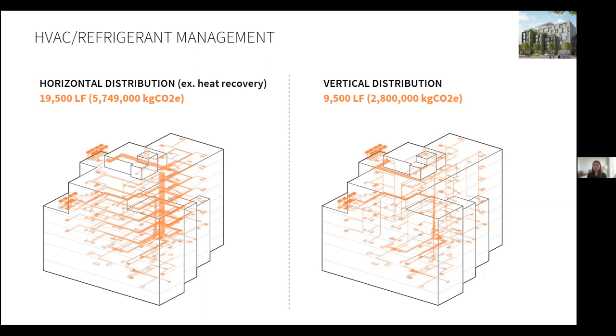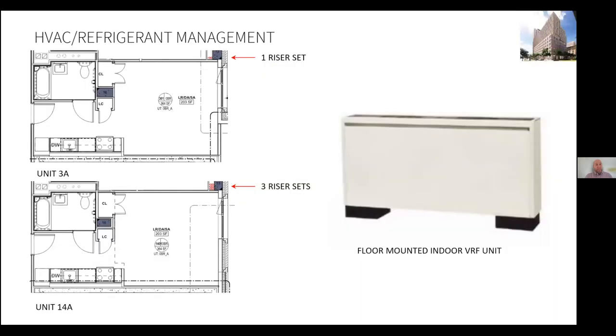Now, Joe will talk about how this will look on a much bigger building. So since Cooper Park is an 18-story building, we're also using a vertical distribution system zone per facade to provide that additional tenant control. The biggest difference comes in the increased height, which needs more coordination with the risers for the VRF units. On this building, we're having to coordinate an extra two sets of risers for the upper, middle, and lower zones of the building. And as the risers go down the building, those risers are then reduced as the supply is no longer needed.